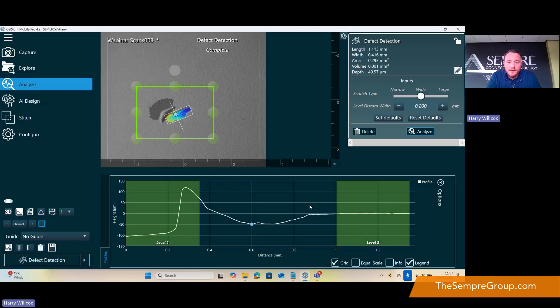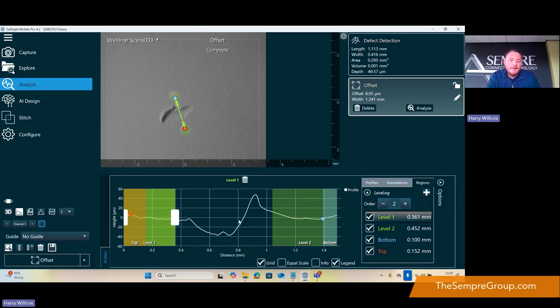So the same principle again, if I go into my modular scan, I can look at this in a couple of different ways. What I'm going to do is just run my defect detection. I'm going to draw a box around the sample, analyze, and then define the feature type that we're looking for. So I'm looking for a wider defect, analyze, and you can see it's captured the step height. Other ways that we can measure this feature is I can profile the data set, and you can see we've got our mark here. And then I'm able to remove the unleveling effectively of the sample. So I can draw a boundary here. You can see that we're on a slightly curved surface. And if I go to my second order function, it's flattening out that data set for me to be able to find the minimum to the side, which is this area here. So that mark is looking at about 36.4 microns deep across that surface area.